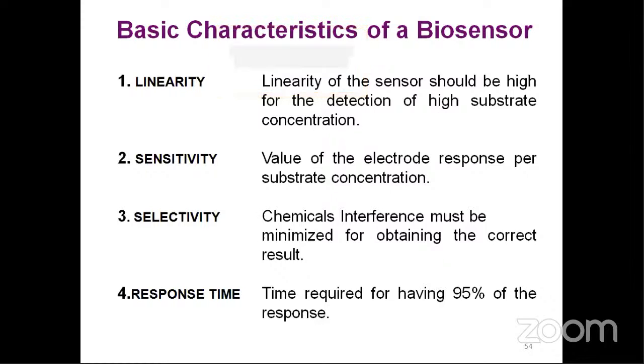The basic characteristics of a biosensor are linearity, sensitivity, selectivity, and response time. Linearity of the sensor should be high for the detection of high substrate concentration. If it is not linear, it does not provide a correct result. Then sensitivity: once you apply a sensor and put a chemical, the reaction should take place immediately, rather than the receptor taking a long time to absorb that chemical. Response time also plays a vital role, because if the response time is very high, nobody is willing to take up that work. For example, for testing COVID, they earlier said 2 days to get your result; now they are providing results within 2-3 hours. The main thing is how much time we need to spend to get the result.